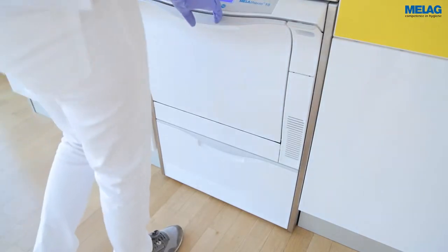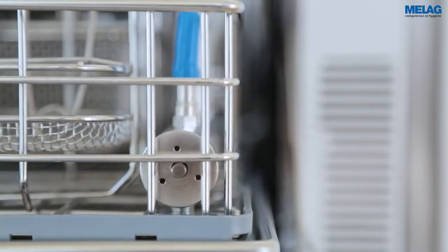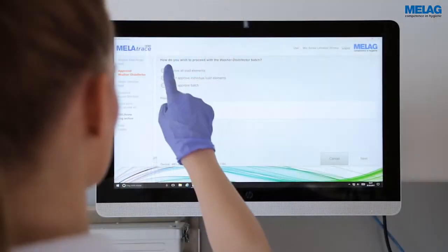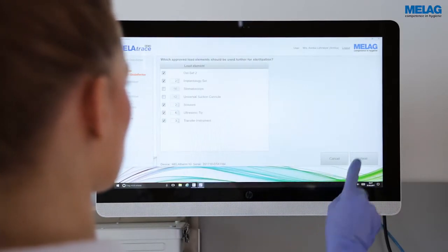The control display of the central filter enables direct verification of the decontamination of the hollow instruments. The operator can perform a visual check of the cleaning result, which is documented with MELAtrace.